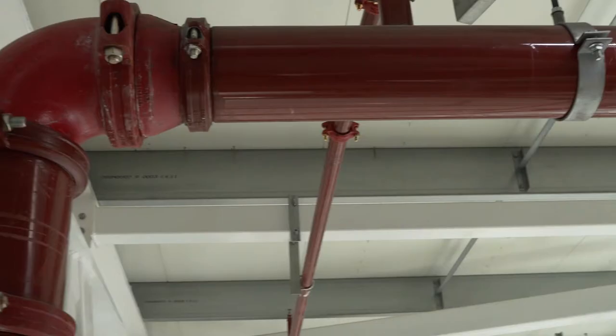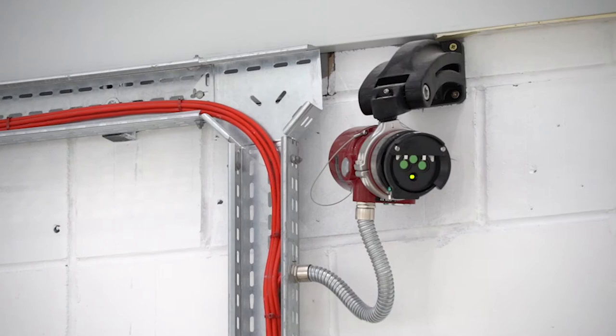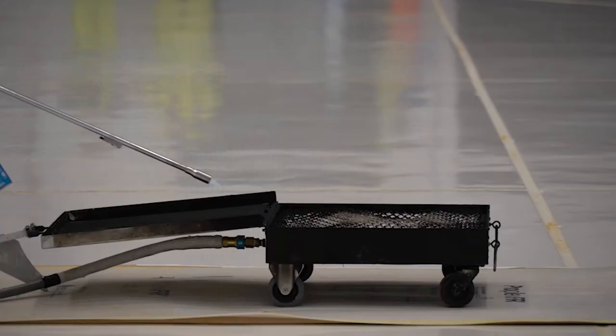The pumps feed the sprinkler and foam suppression systems. The sprinkler system is high level in the hangar, and it's also in the accommodation, plant rooms and storage areas. The foam suppression system is a low level system, and the activation is done by flame detectors, which detect a flame by two flame detectors at any one moment.